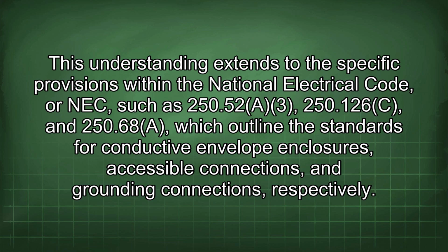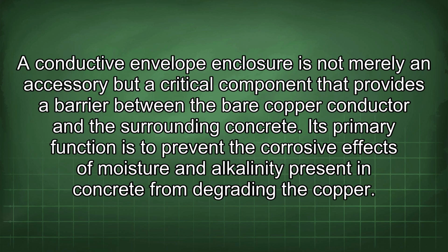250.52(A)(3), 250.126(C), and 250.68(A), which outline the standards for conductive envelope enclosures, accessible connections, and grounding connections, respectively. A conductive envelope enclosure is not merely an accessory, but a critical component that provides a barrier between the bare copper conductor and the surrounding concrete.